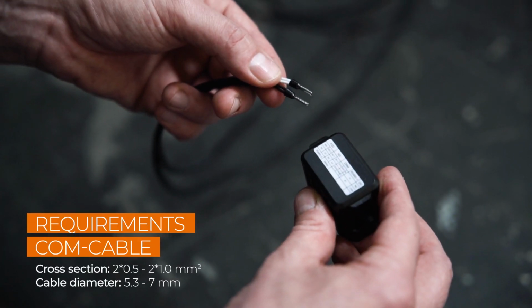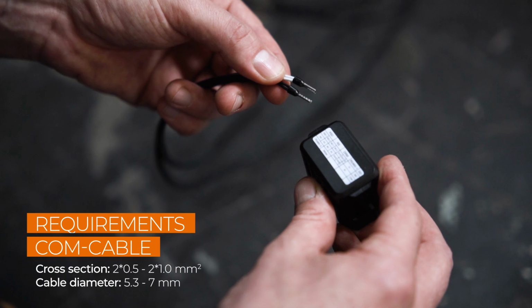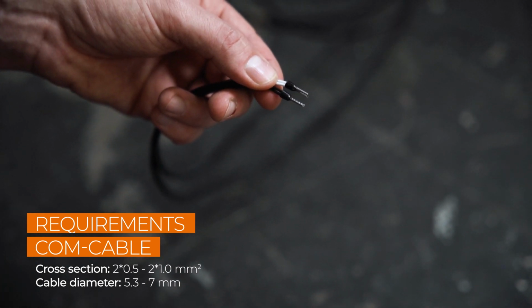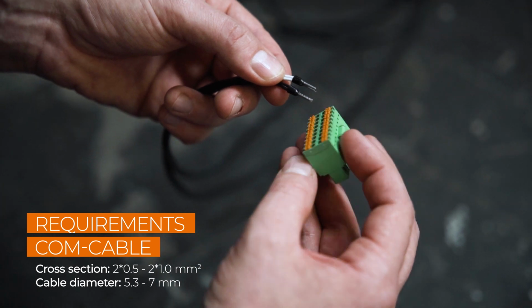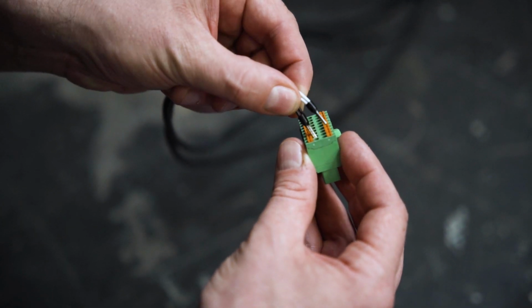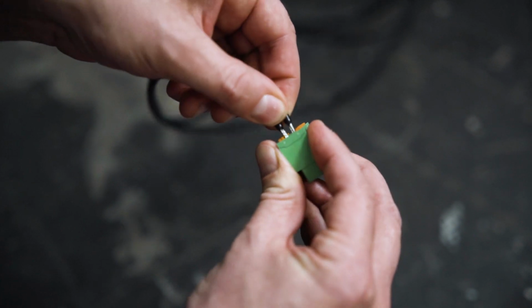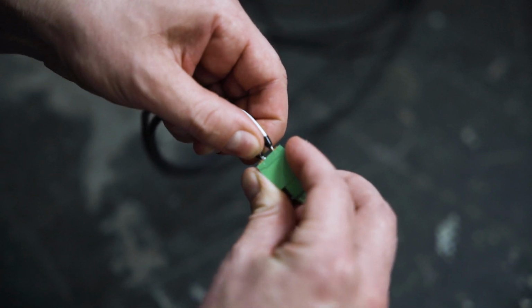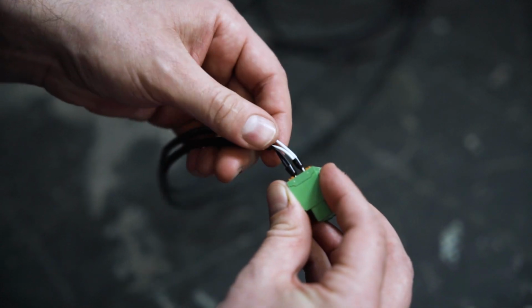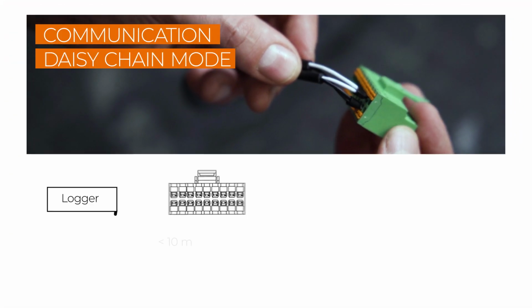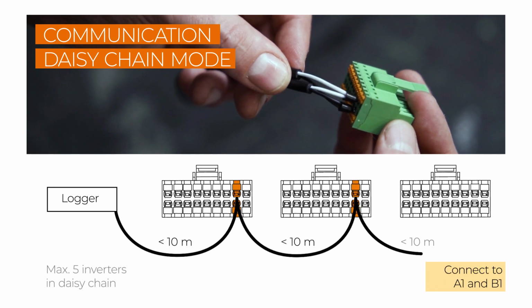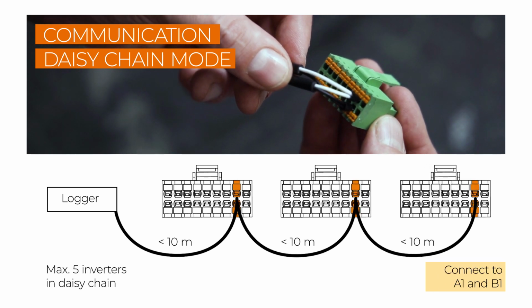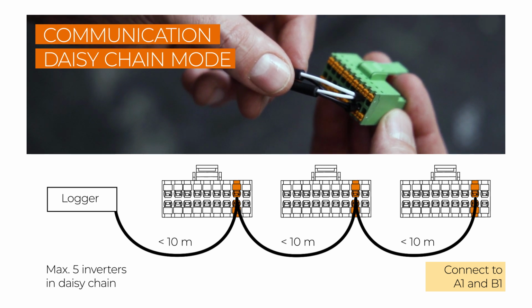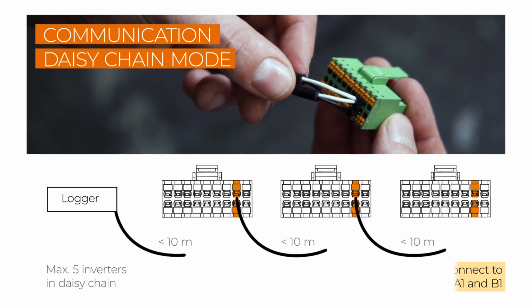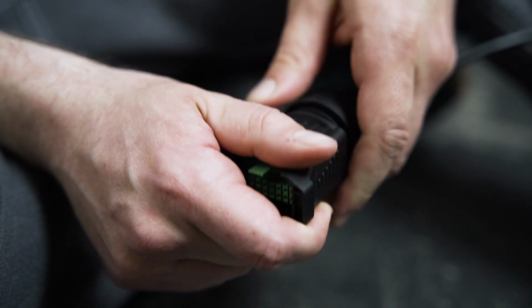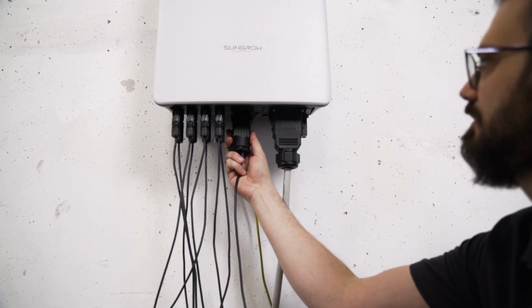A maximum number of 5 inverters can be connected in daisy chain mode. If necessary, you may have to fit the cables with the end sleeves before you push them into the plug. Connect the cables to the ports A1 and B1 at the RS485 interface of the inverter. The first inverter in daisy chain mode can be connected to the RS485 port of the logger. The cable between two inverters should be no more than 10 meters. When daisy chain mode is being used, the WiNet-S can't be used as communication device. Plug everything together, screw it, and plug it in.